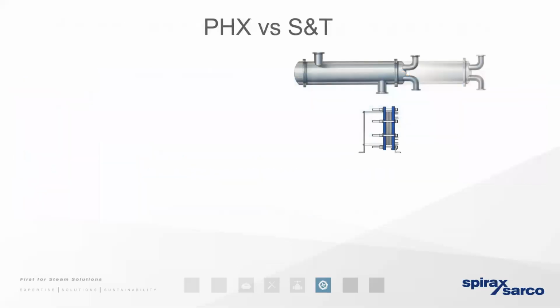With regards to utilizing the steam efficiently, we know that there's still a lot of steam using sites out there that are using shell and tube heat exchangers to generate sources of hot water for process purposes, rather than the modern, efficient, instantaneous plate heat exchanger. And because an instantaneous plate heat exchanger has got a far bigger and more efficient heat transfer surface area, we don't need to hold any water in the secondary side, hold water in storage. So that smaller heat exchanger means that we've got less water held in storage, so we've got less radiating loss, less standing loss. And it also means that we've got a significant reduction of footprint that can result in smaller plant rooms.